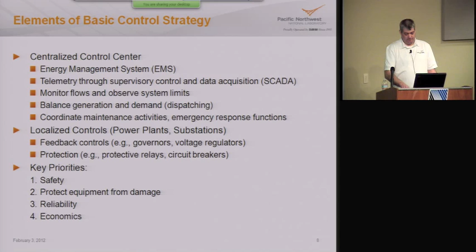Now, I promised I'd talk about this frequency thing, and this is really key because I'll come back to it later in the talk. When we balance supply and demand, we're managing the frequency on the system. In North America, we have a 60 hertz grid. Other places in the world, the nominal frequency is 50 hertz, but the same principles apply. On our 60 hertz grid, when supply and demand are matched, the grid will be at that stable nominal frequency of 60 hertz. Anytime there's a mismatch, it will either speed up or slow down, and all of the generators and all of the rotating equipment, including motors and everything connected to that grid, will speed up and slow down accordingly.